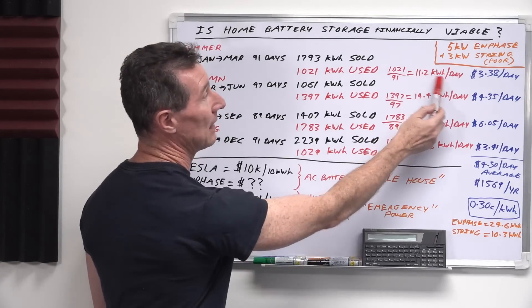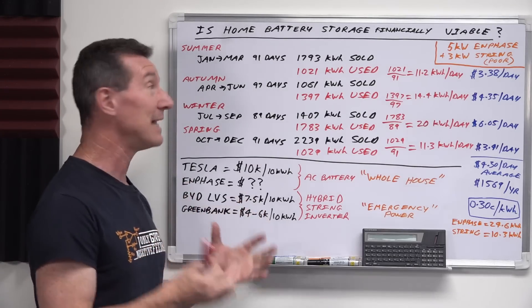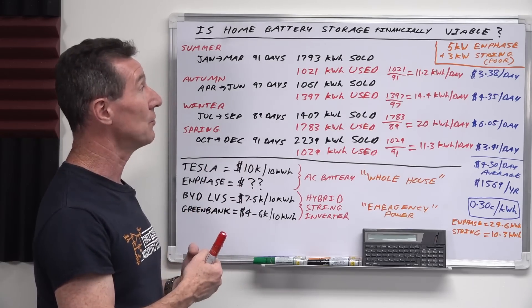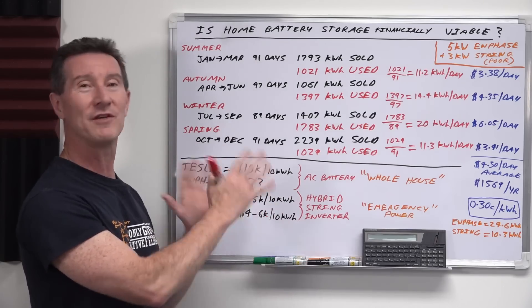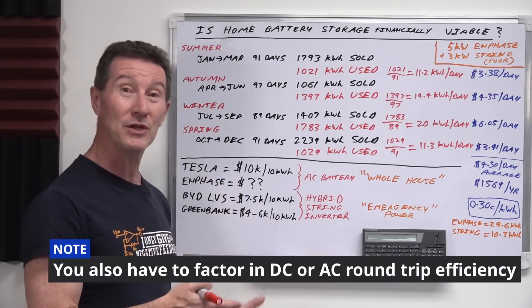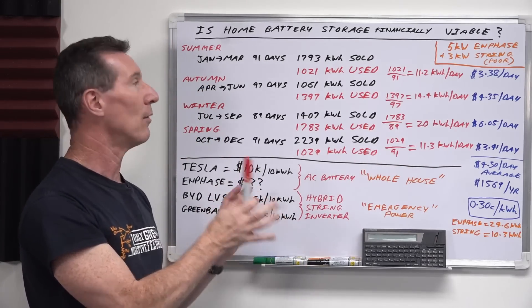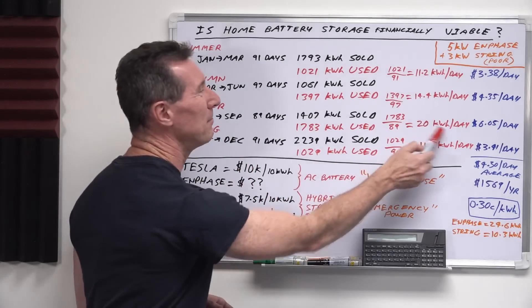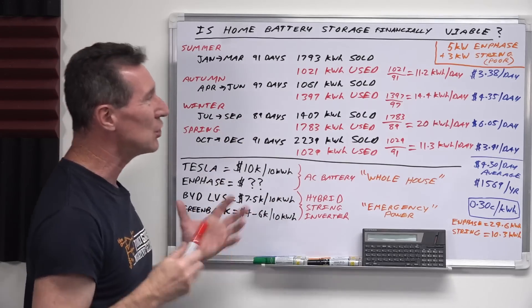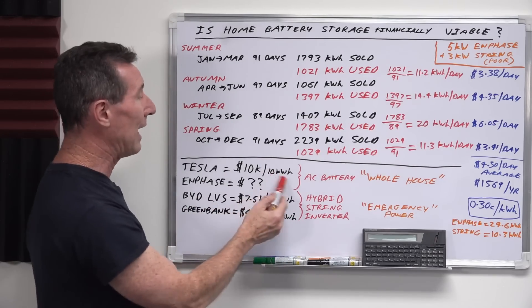What size battery do we need? Well, it pops right out of the numbers: 11, 14, 20, 11 kilowatt hours per day is what we're pulling back from the grid across the seasons. If we can extract that amount of power during the day — and this is all on average; a bad day means you'll draw from the grid — it looks like we need at least a 10 kWh battery, maybe 15 kWh. A 20 kWh battery might be overkill for the worst season and costs a lot more upfront, so I'm standardizing on a 10 kWh pack for pricing purposes.